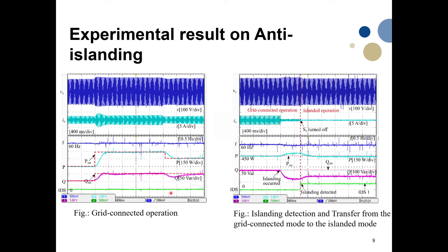In another example, we created an islanding condition. It took 650 milliseconds — 0.65 seconds — to detect the islanding condition. This detection time can be designed by the system designer to be shorter or longer depending on requirements. According to standards, keeping it within two seconds is acceptable. Here we keep it at 0.65 seconds, which is within the standard.